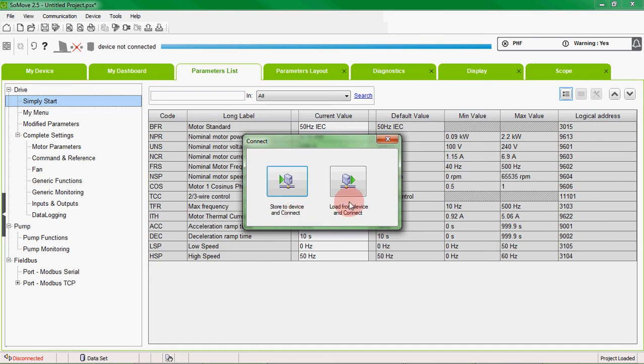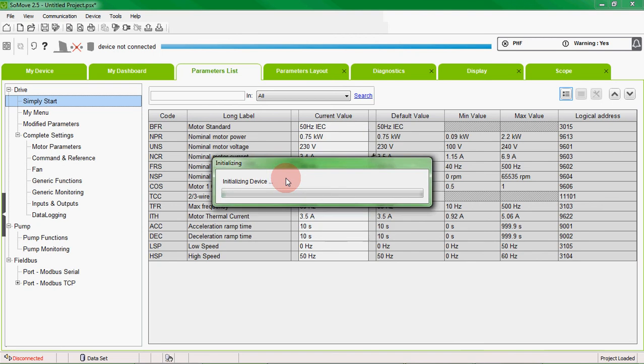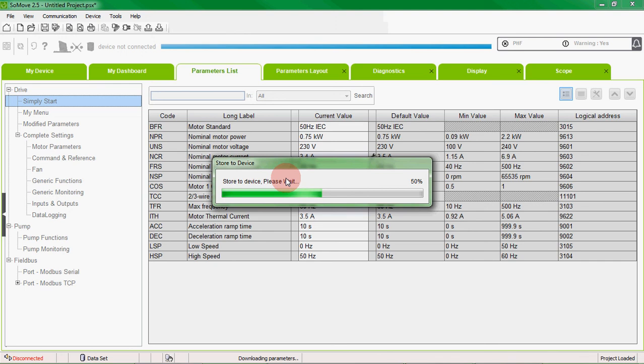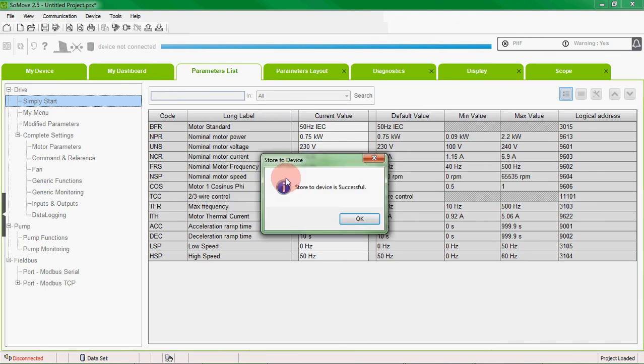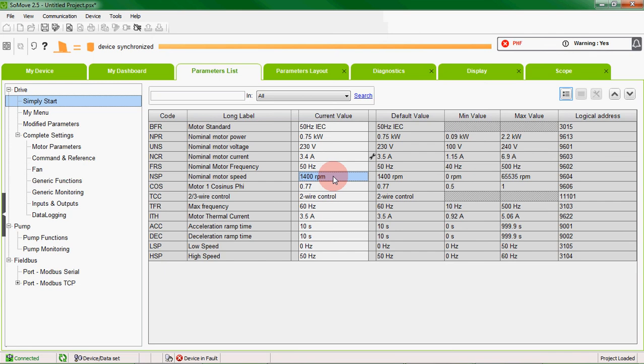If we want to push the offline parameters onto the VSD we select store to device and connect. If we want to upload the parameters from the drive to SoMove we select load from device and connect. But in our example we have made a change to a parameter that we would like to put onto the drive, so we store to device and connect. And as you can see the device is synchronized and our parameter has changed.